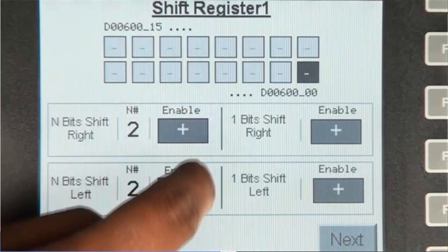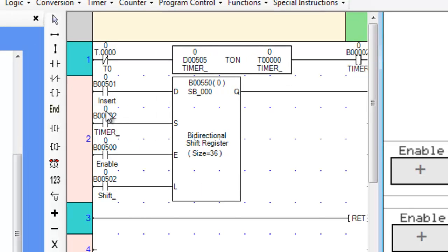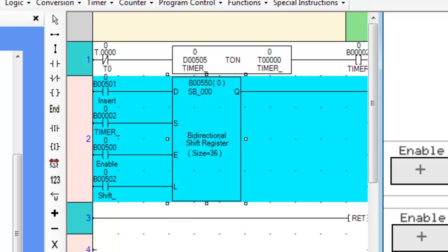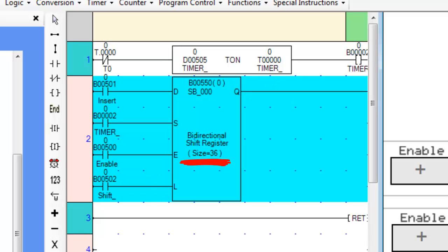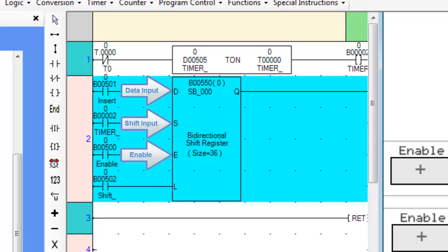Let's go back to the ladder logic and review the rest of the shift instructions. The bidirectional shift register works exactly like the regular one bit shift except for a few minor differences. First, it has four input lines rather than one, and only one output line. Notice the size parameter — the instruction only takes coils rather than registers. We have a coil table where n is the number of coils and it works exactly like a register table. The four inputs are D for data input, which is either a 1 or a 0, S for the shift input, and E for the enable input. This instruction will only execute when both the enable and the shift inputs are turned on. When the enable input is turned off, all coils in the coil table will turn off.